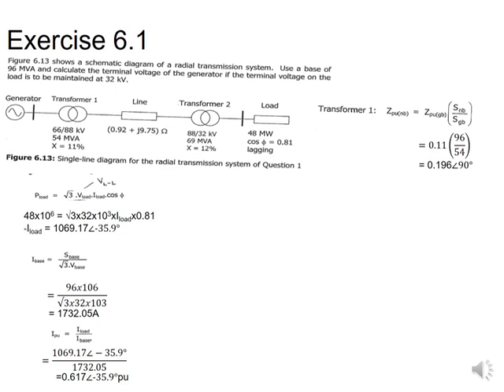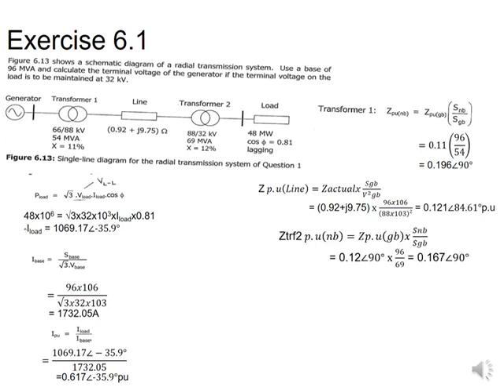We then go through all the different units in the circuit and calculate the new Z per unit. For transformer 1, you multiply the 11%, which is 0.11, by the new S base of 96, then divide by the 54 MVA rated on the transformer. For the line, the formula is Z actual times S over V squared, giving 0.121 at 84.61 degrees. For transformer 2, it is 12% times 96 over 69.